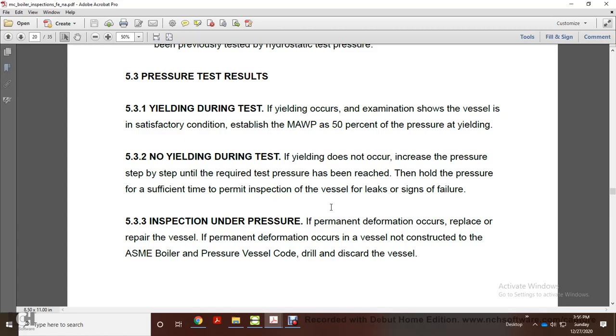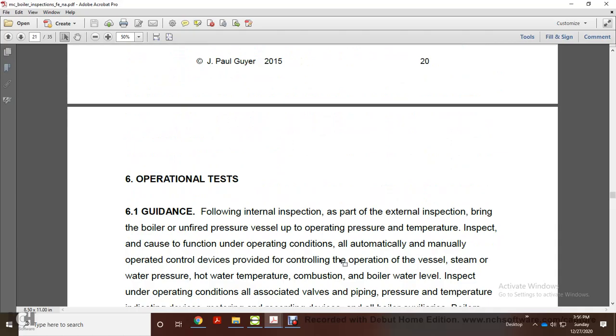5.3.3. Inspection under pressure. If permanent deformation occurs, replace or repair the vessel. If permanent deformation occurs in a vessel not constructed to the American Society of Mechanical Engineers Boiler and Pressure Vessel Code, discard the vessel.